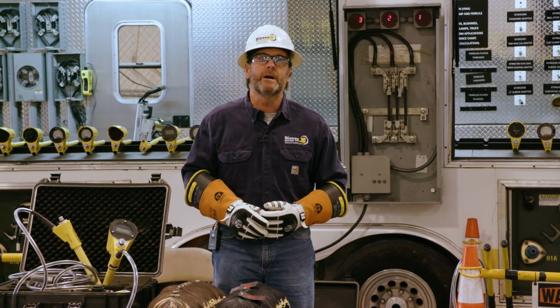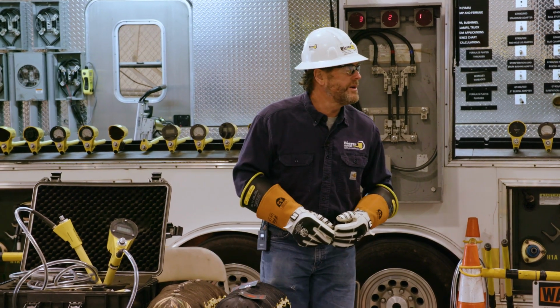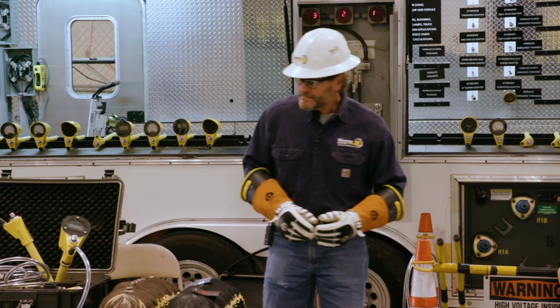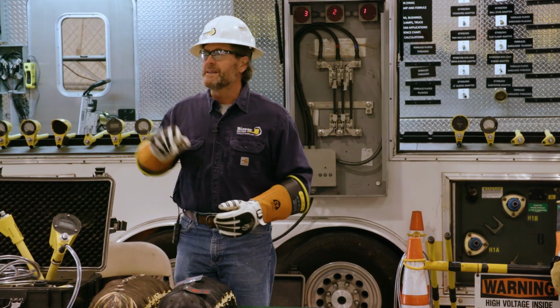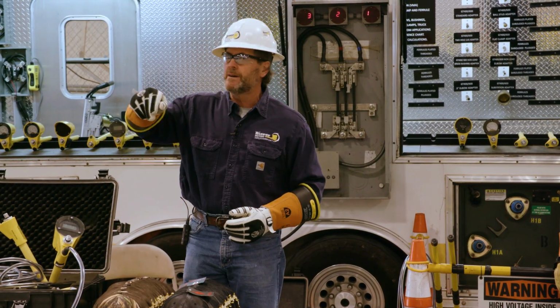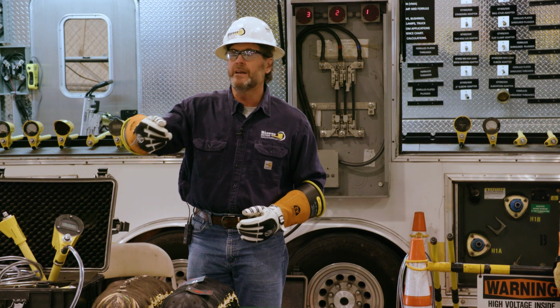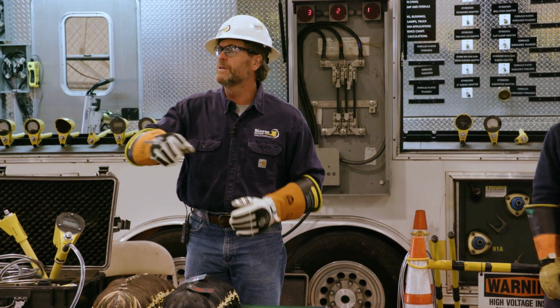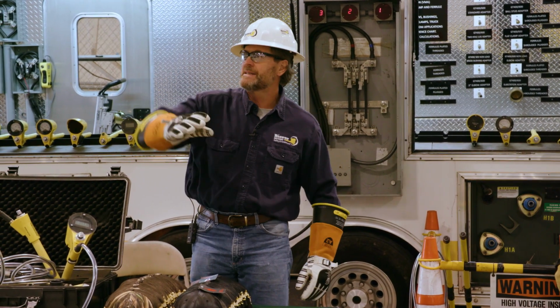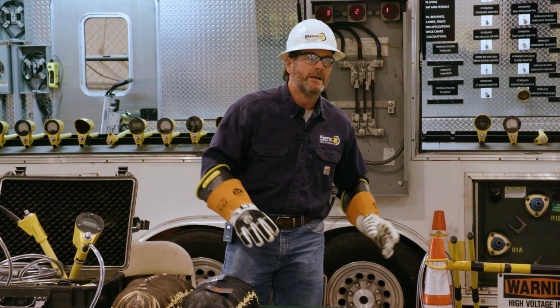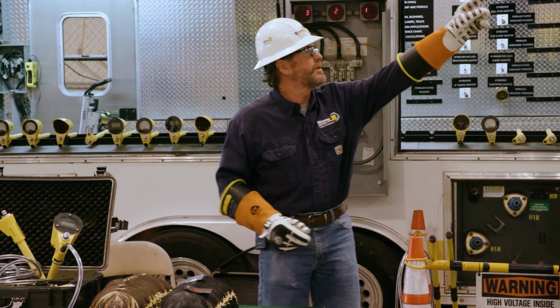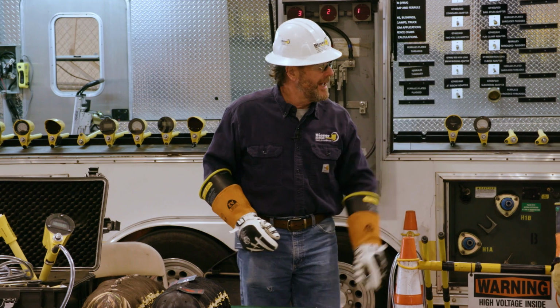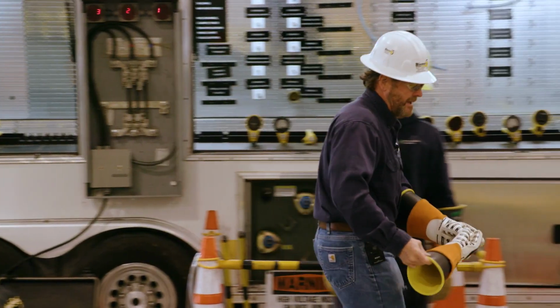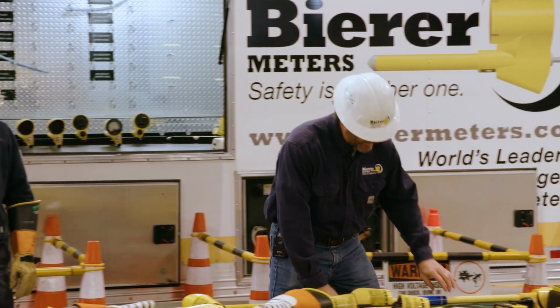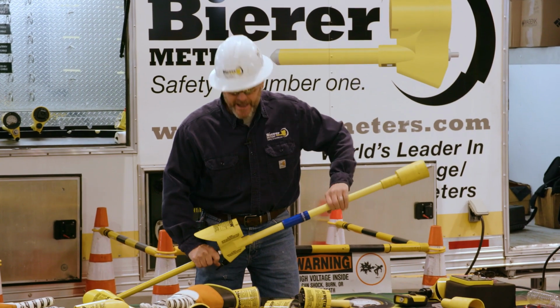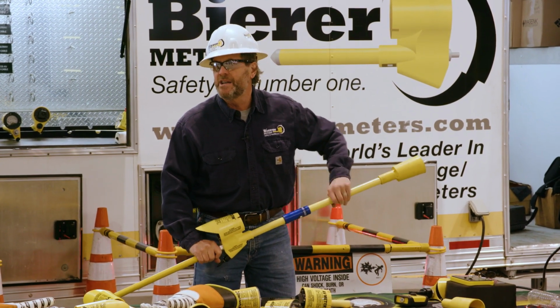Okay, the PD800W. So remember, when you're doing wireless phasing, you always want to take your tool and put it in the degree position. Not URD, not overhead, because we're not looking at potential, we're looking at phase angle. That's it. So you're going to take your reference probe that's hanging up there and your meter probe. Here, I'll get this ready. And your meter probe that's here, you want to always go DEG for degrees.